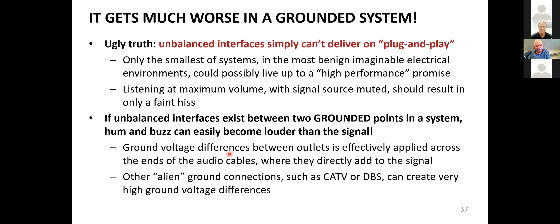Now, if I had that same system and grounded both ends, the few millivolts that might be induced in here become much bigger—10 or 20 times bigger than the 316 microvolts I had without a ground connection. That's why people are so prone to put a lifter in and interrupt these ground connections, getting one of those 3 to 2 prong adapters. DJs are famous for this, and so are home hi-fi enthusiasts, because it's the cheap and dirty way to make a noise go away.